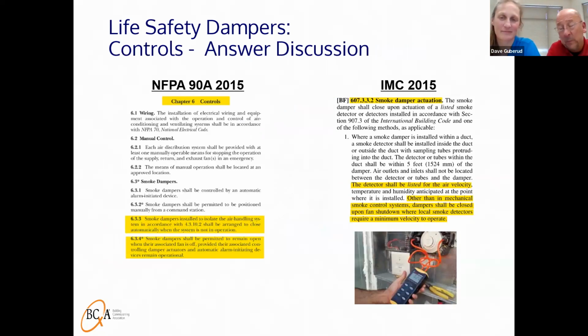Now, in Wisconsin, we move very slow, like we walk slow, but we talk fast. So we're still using 2015, but it does indicate that if a duct smoke detector does not have the ability to appropriately read smoke when there's no velocity past it, then the damper should close. So that's kind of the nuts and bolts of it.